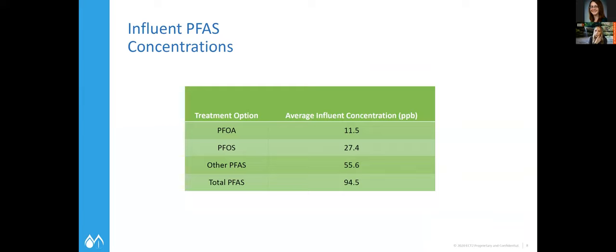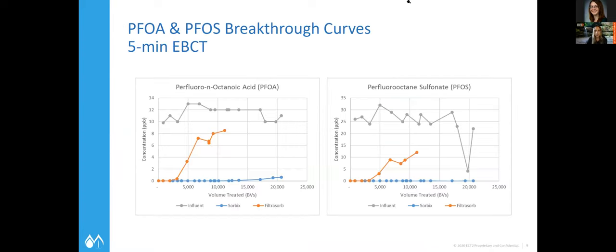A little more background on the site: influent concentrations of PFOA and PFOS are in the parts per billion range — a little higher concentration than the parts per trillion typically discussed for drinking water. The goal at this time was to hit 70 parts per trillion coming out of the system, though they are getting to non-detects. Initial breakthrough results from piloting were done at a five-minute empty bed contact time. As you can see, the bed volumes treated for the resin — the blue line — is much higher before hitting breakthrough than the orange line, which is the granular activated carbon.